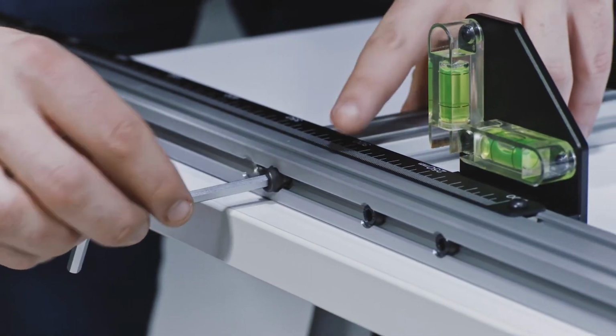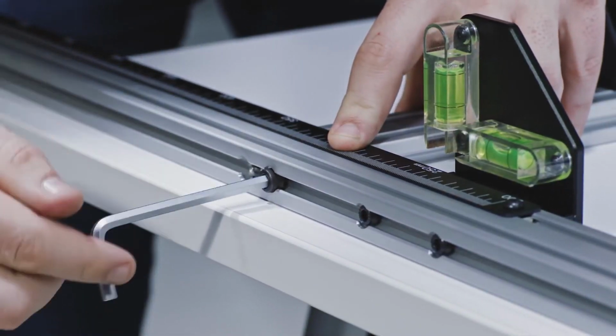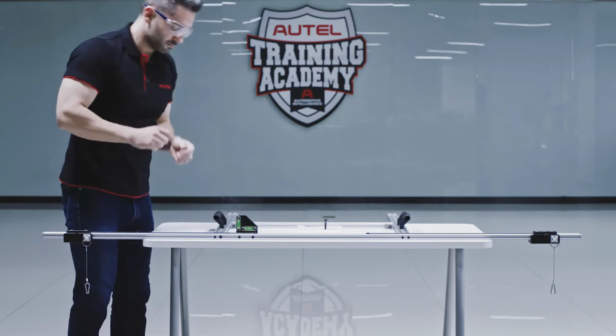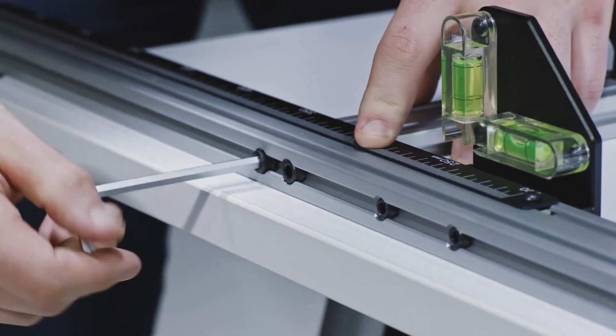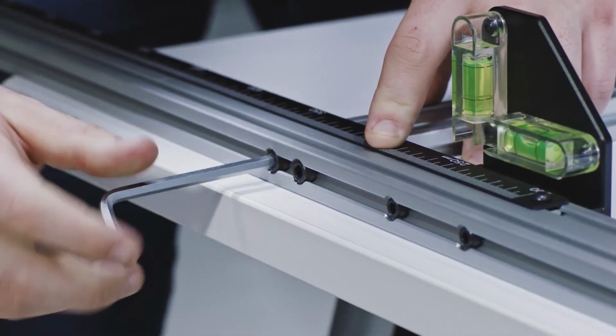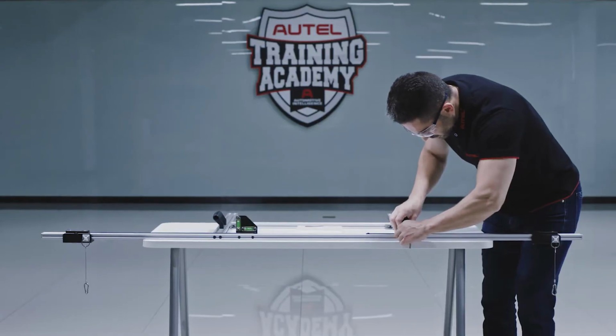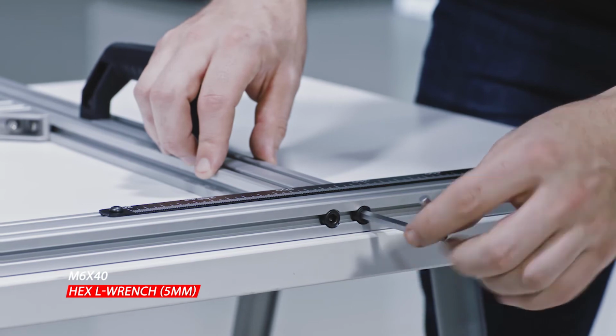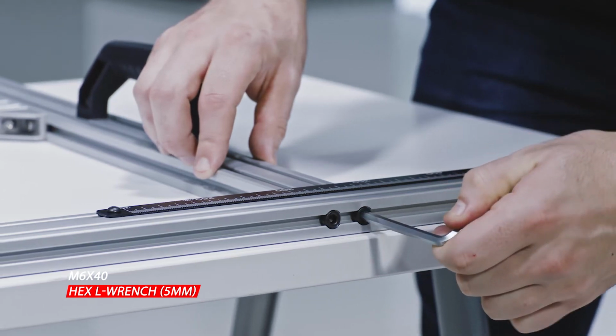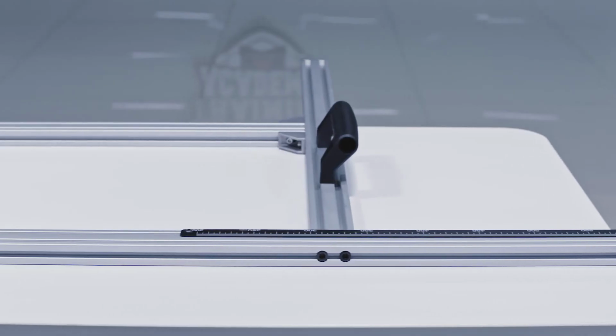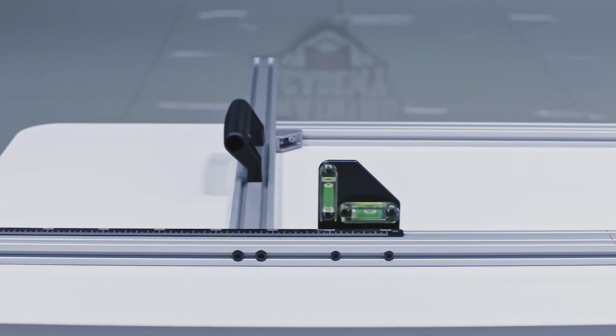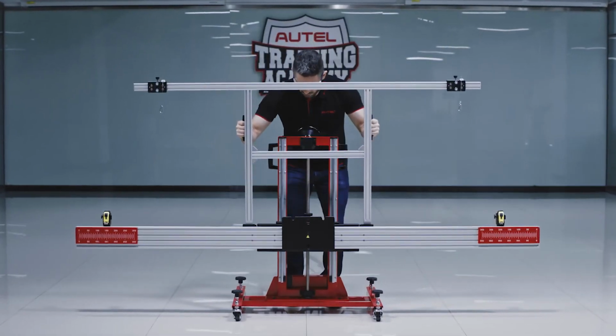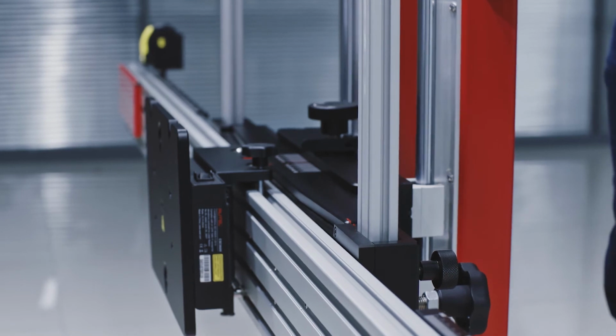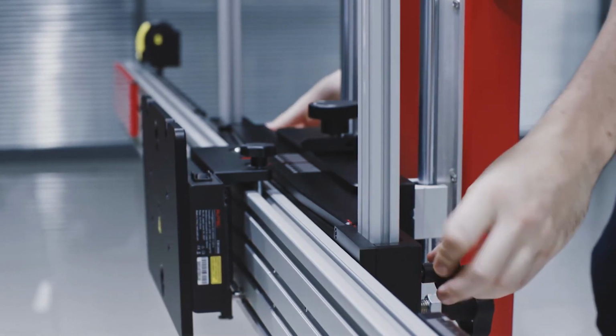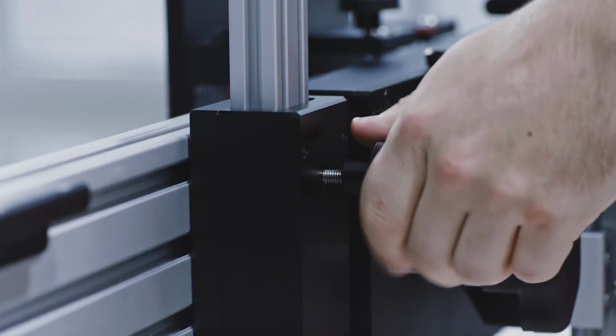Place the slide bar with the bubble spirit level facing up. The levels should be on the same side as the handle. Align the 4 screw holes on the slide bar with those on the left and right poles. Insert bolts and tighten with the hex L-wrench 5 mm. Insert the left and right poles into the slots on each side of the lifter of the calibration frame. Tighten the hand knobs.